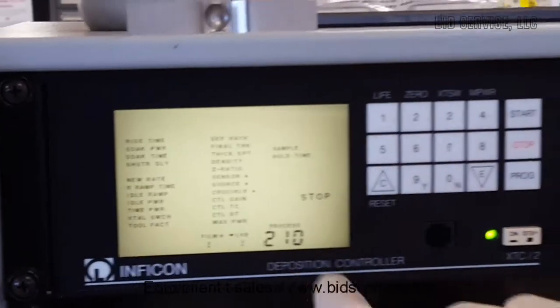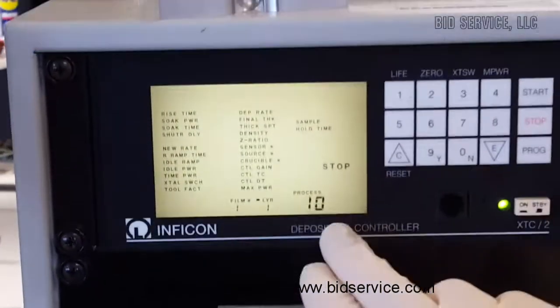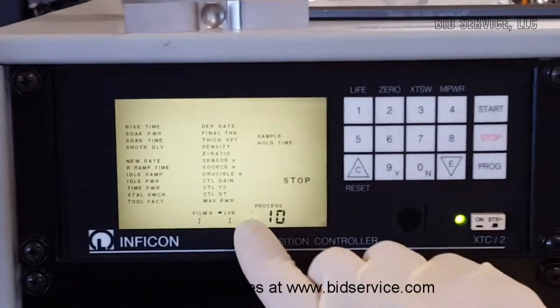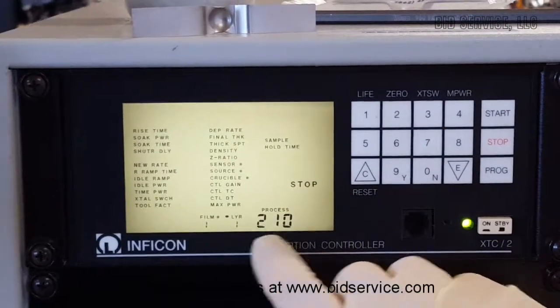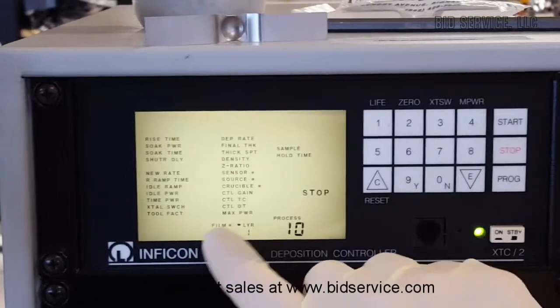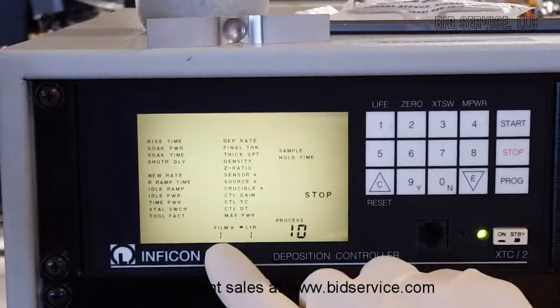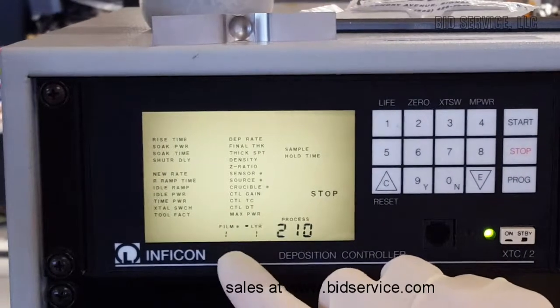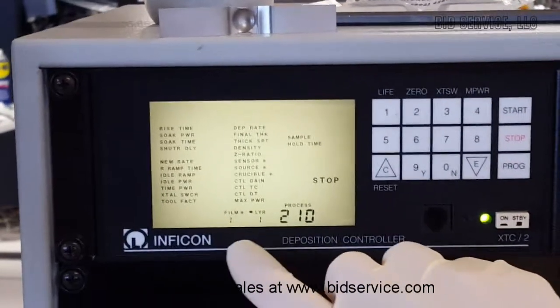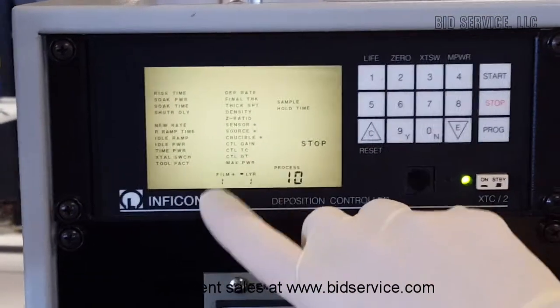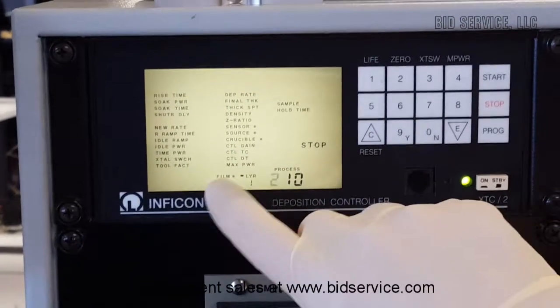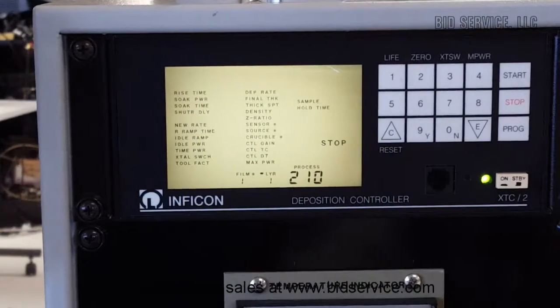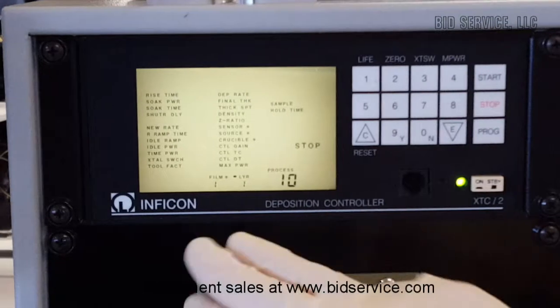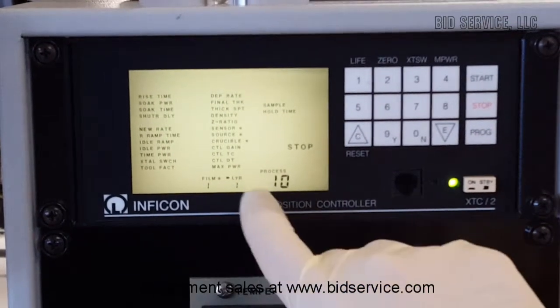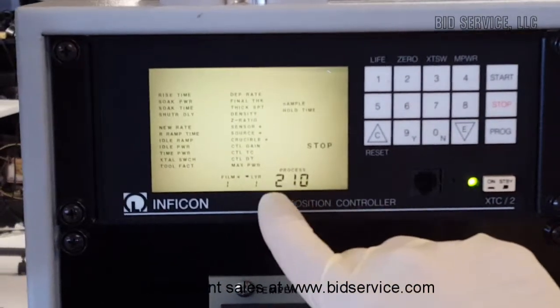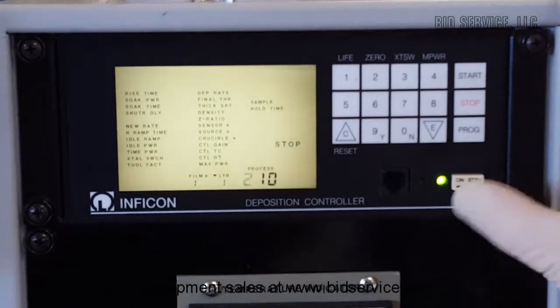So that's the process that we have running. Again, you can do 3 separate layers, and then each layer has a film. You can identify a film for that layer. I think you can program up to 9 separate films in here. So say you had other metals you're depositing at different rates, you can create a recipe for each film. Again, this is explained in the manual. But what we're going to run here is we're going to put 2 down first and then 1.